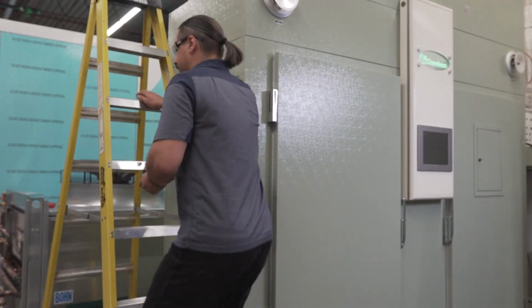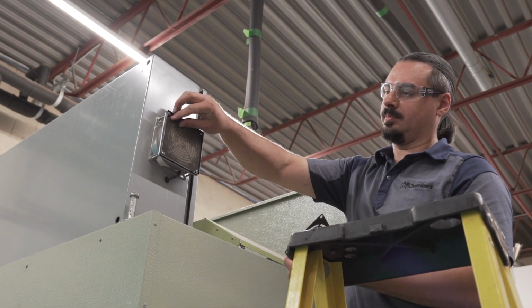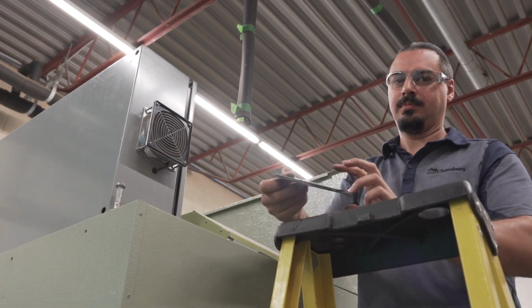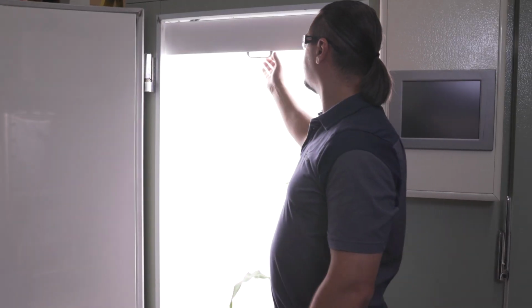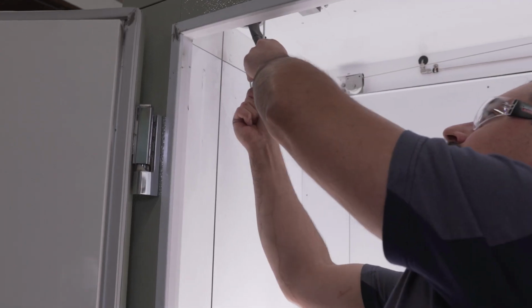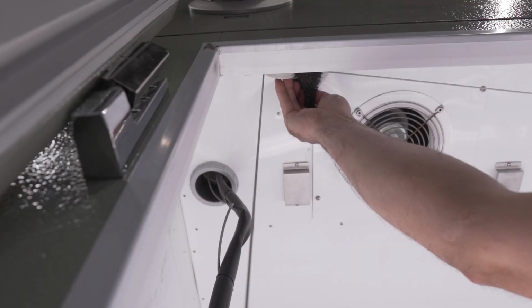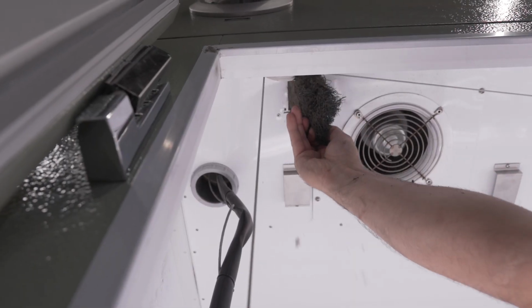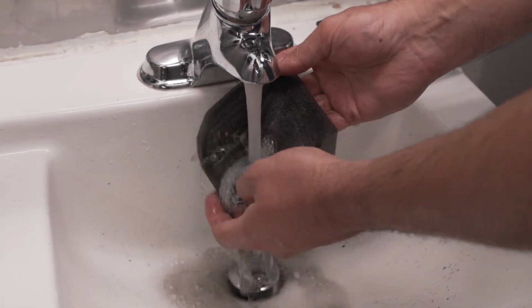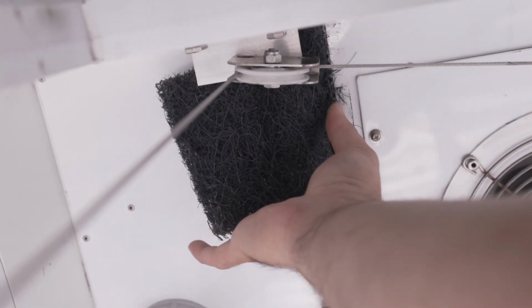Every 6 months, all chamber air filters should be cleaned. Air filters are located on the fresh air and exhaust dampers and near the fans blowing into the control panel. Clean filters using compressed air or a vacuum, or by rinsing them with tap water and letting them air dry before putting them back in.